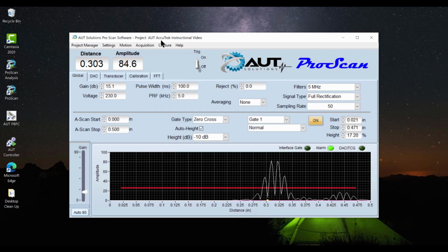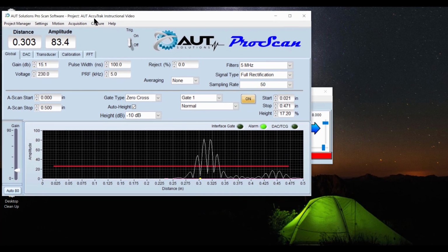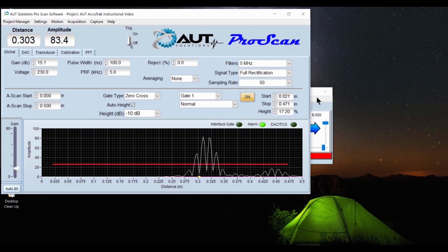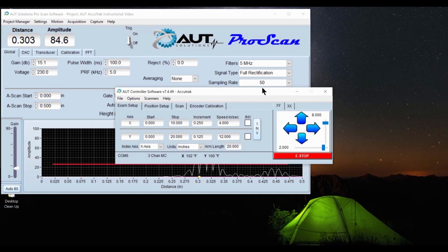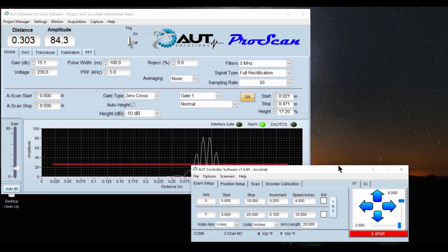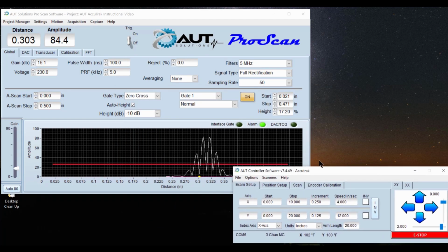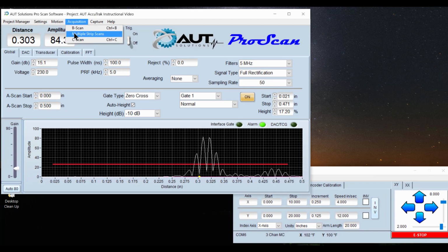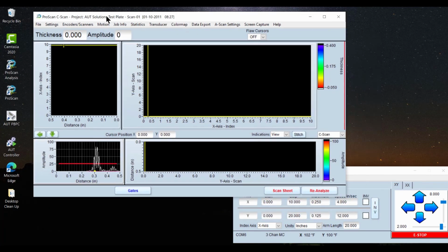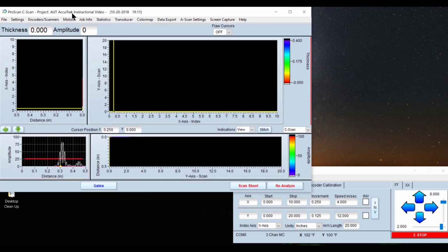So what we're going to do, our first scan is always highly recommended to be the test scan, because 9 times out of 10 there is a simple small feature that we forget to set up that would allow our scan to come out the way that we want. So we will simply go up here, click on acquisition in our A scan settings. We will select C scan. If you were doing a B scan strip scan or a manual B scan, you would select B scan right there. So we will go ahead and go into our acquisition window.